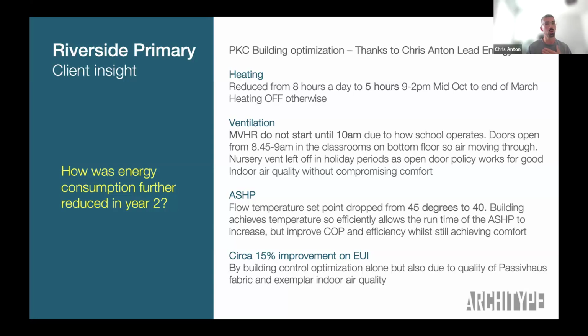We found out that because the building's being used to let kids in and out, doors were being left open, and that was cooling down the building. Because you're using the heat within the building to feed back cleaner air, what was actually happening is it was pulling out warmer air from the classrooms and pushing in colder air, just because the doors were being left open. So we made some simple alterations.